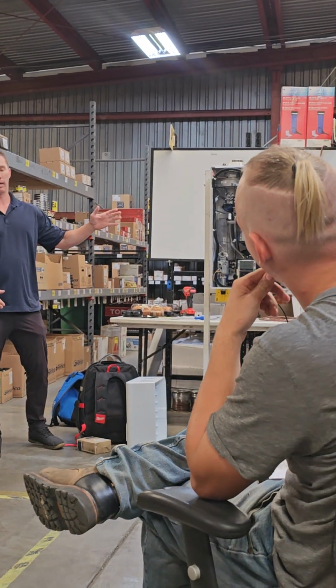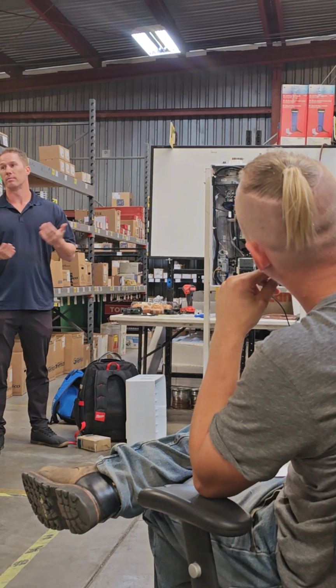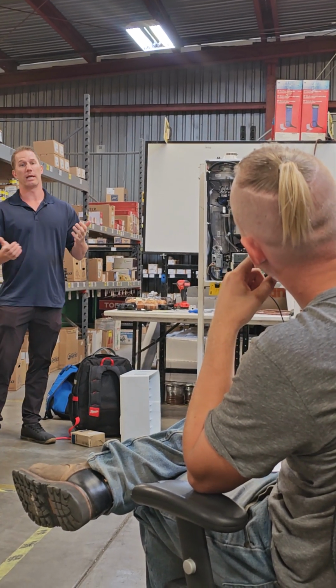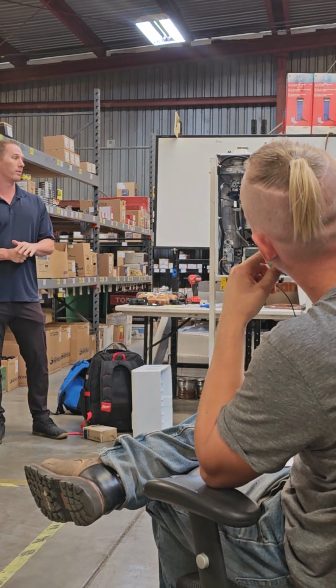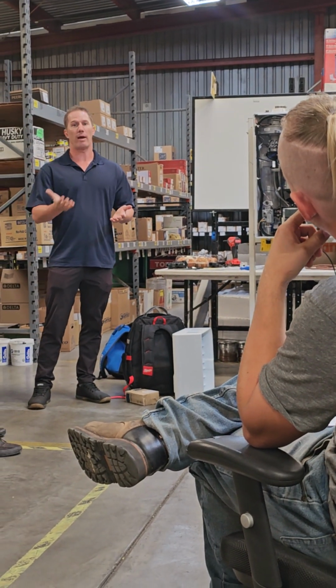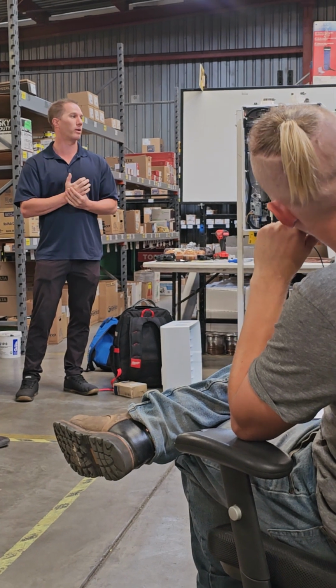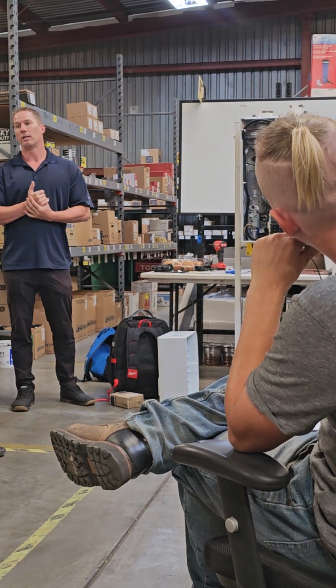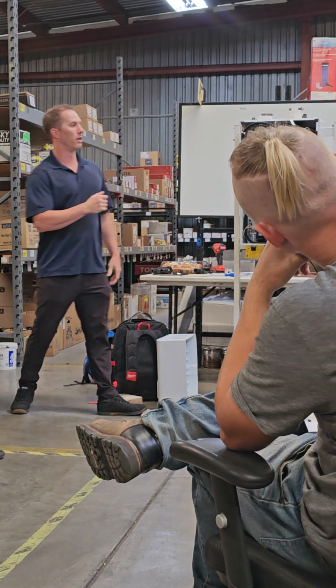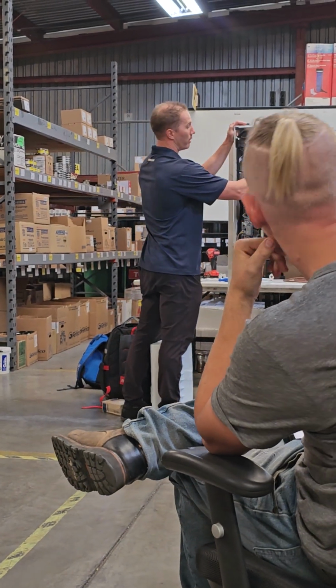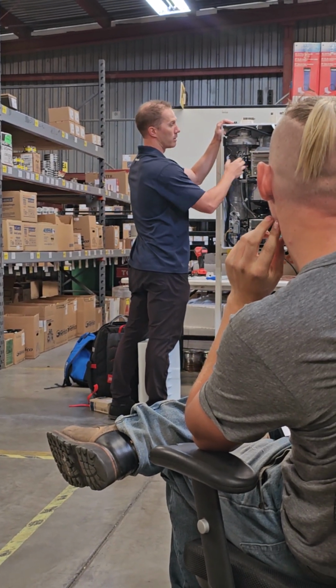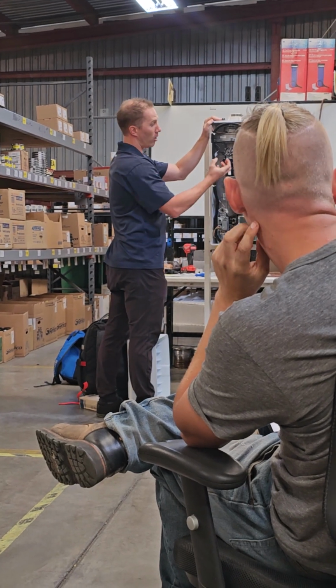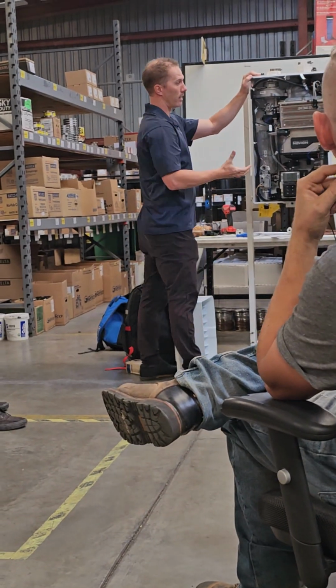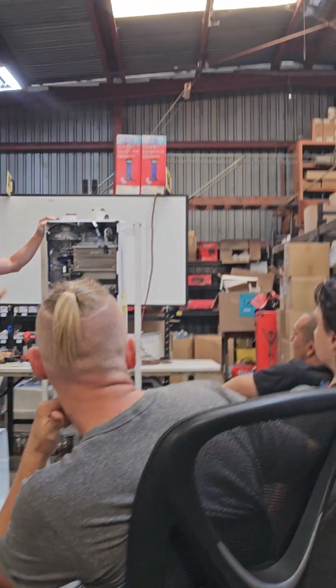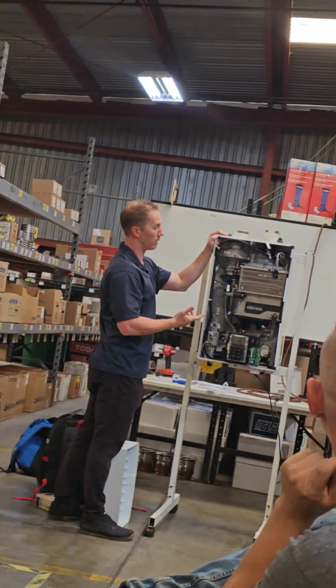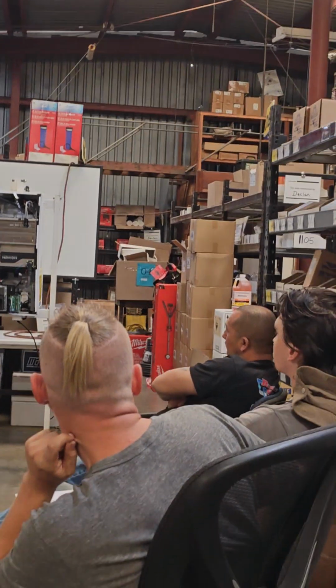So cleaning the unit, once a year. I tell the homeowners, it's just like your car, you have to change the oil periodically, you have to get these things serviced. It's not like a tank water heater where you just don't need to do it. It's one of those things that needs to be done because the scale builds up in the heat exchanger and it slows down the flow. Also, if it slowly builds up in there, it can't heat the water fast enough, so efficiency is going to drop, and the heat counts are going to drop.